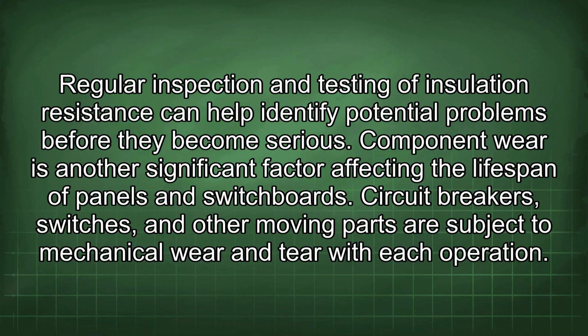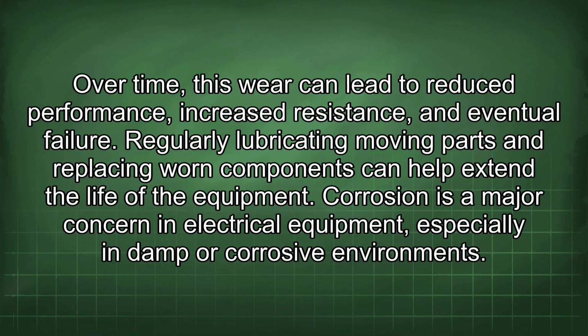Component wear is another significant factor affecting the lifespan of panels and switchboards. Circuit breakers, switches, and other moving parts are subject to mechanical wear and tear with each operation. Over time, this wear can lead to reduced performance, increased resistance, and eventual failure. Regularly lubricating moving parts and replacing worn components can help extend the life of the equipment.